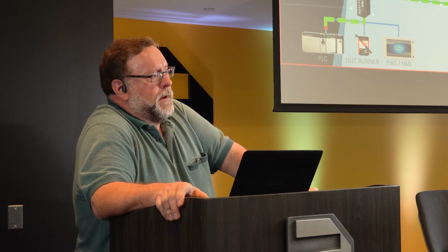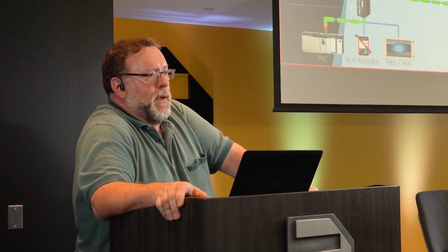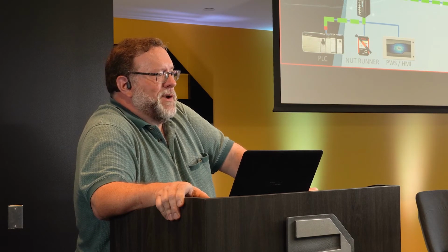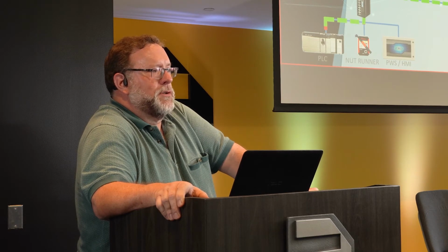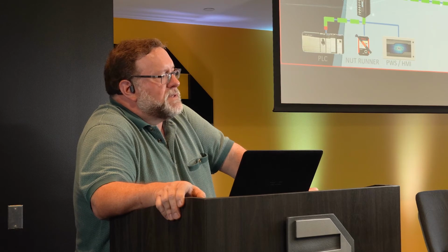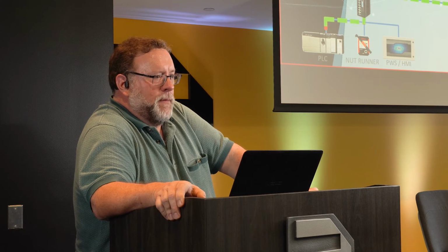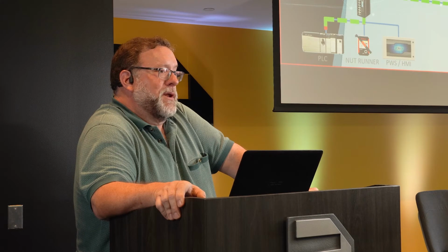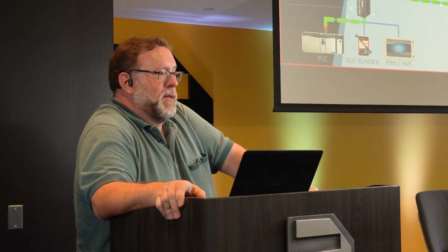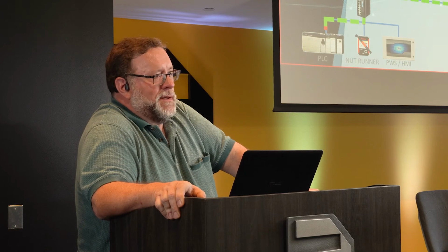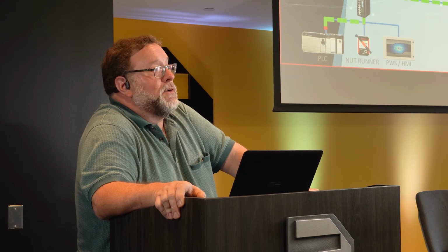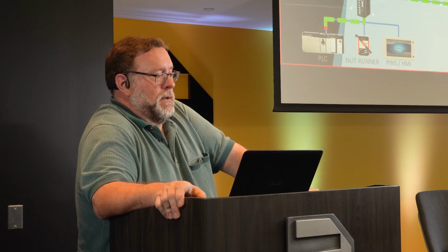One of the biggest challenges that we run into right now is massive amounts of broadcast traffic, because every SDN switch sends every packet that it doesn't recognize to the controller, and the controller has to deal with it. So we have this concept of automated drop flows. Say, for example, you've got an Ethernet IP network running DLR, and you've got that beacon being thrown up at the controller all the time. Beacons are every 50 milliseconds, and basically the switch says, here's a packet. The controller is going to say, no rules, throw it away. Here's a packet, no rules, throw it away. And we do it every 50 milliseconds.